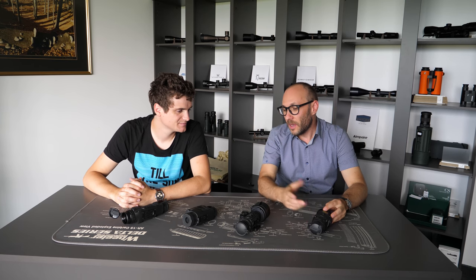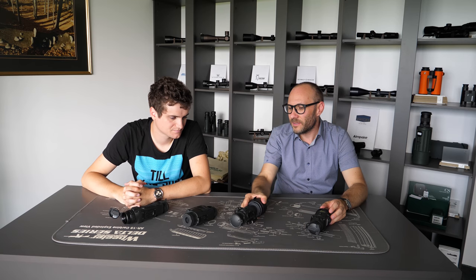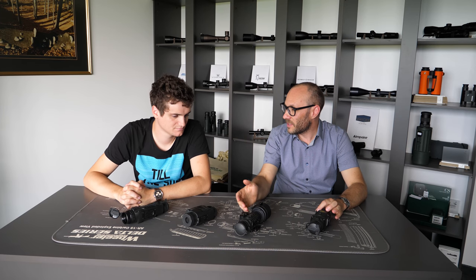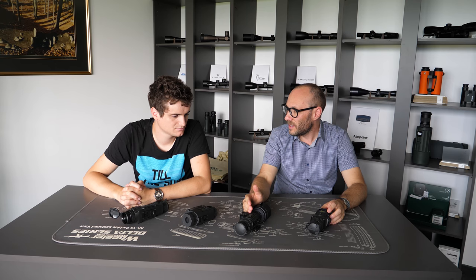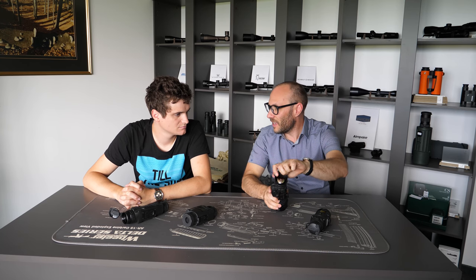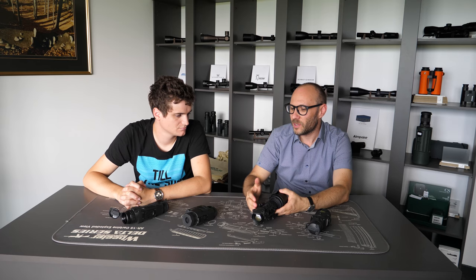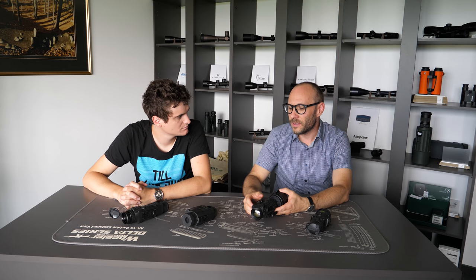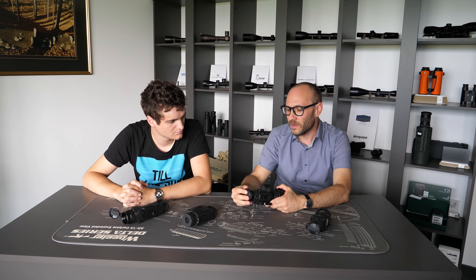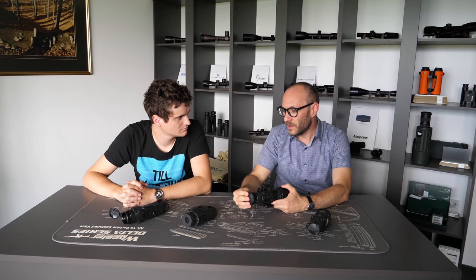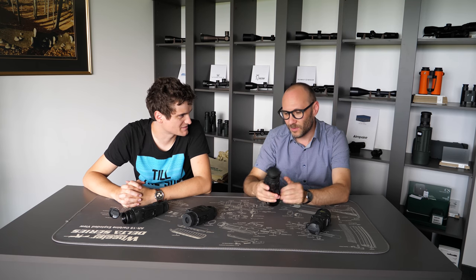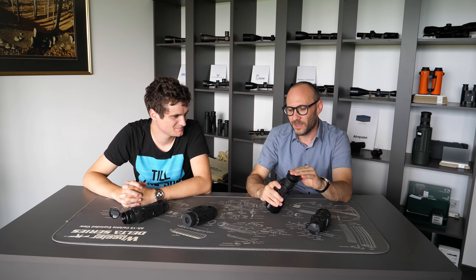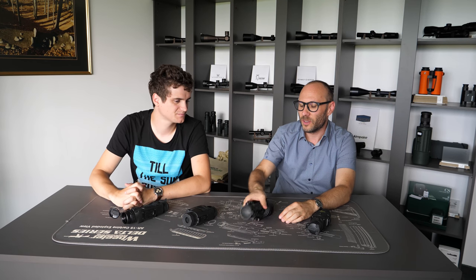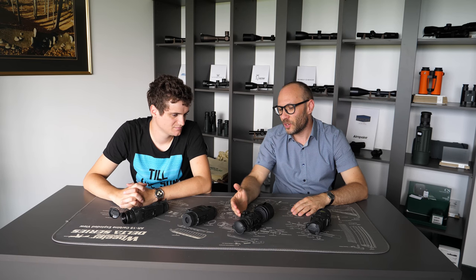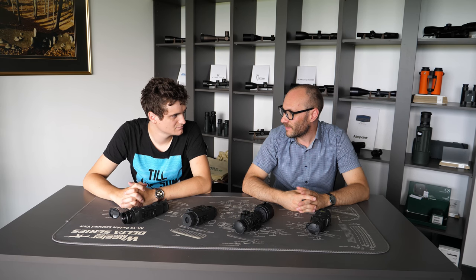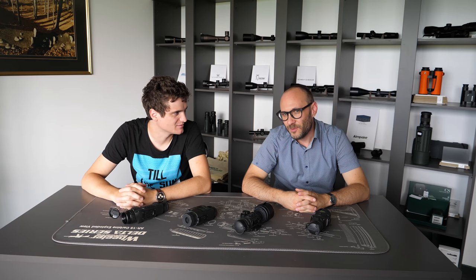No, it's not. It is true that more expensive devices have shutterless calibration without any sound, also in the automatic mode, without the need of closing down the lens. They are automatically calibrated without producing any sound, and this is normally a superior feature, but it comes with a really high price. So this is the difference. Especially when you calculate whether this feature justifies such an increase in price. That depends on the customer, right? Yeah, from customer to customer.